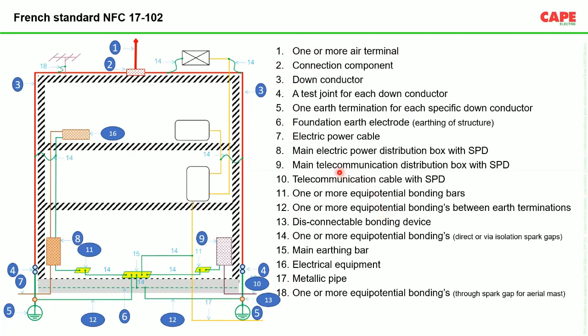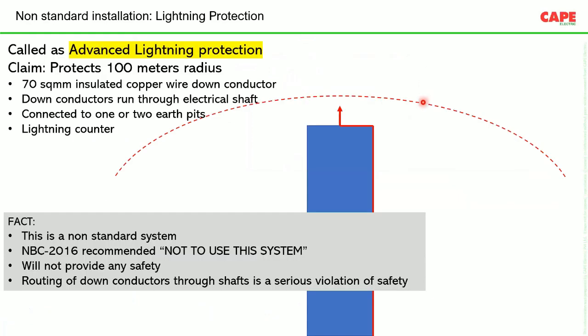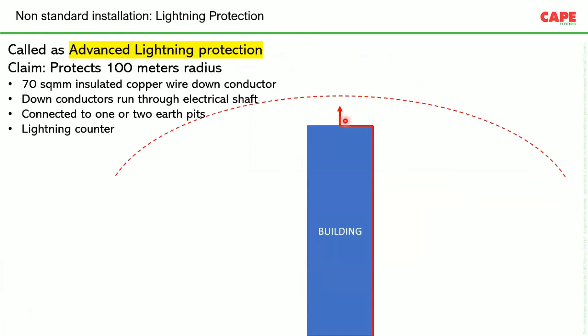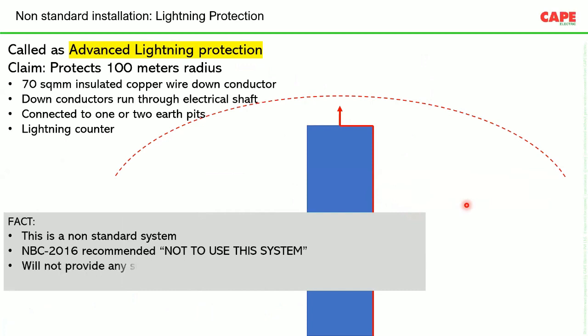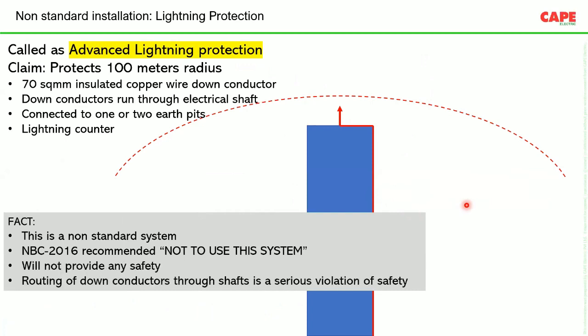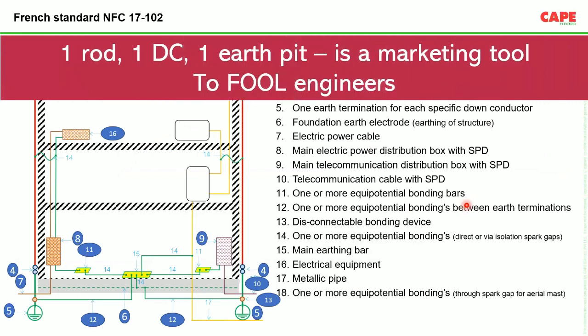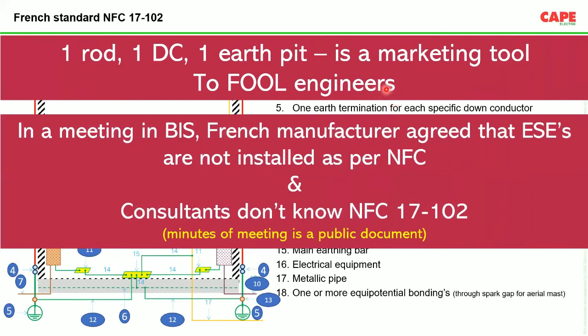Whereas the French code is asking to put an additional rod. Please note, additional rod. Whereas the same system, manufacturers take it to India and they say that one rod protects 100 meters. You take one wire and connect to the earth pit, your lightning current will go like water through a pipe, which is absolutely wrong. So one rod, one down conductor, and one earth pit is a marketing tool. And this marketing tool is actually fooling engineers. All engineers are made fools, because if we know how a high frequency current works, then you will not accept this one down conductor principle.